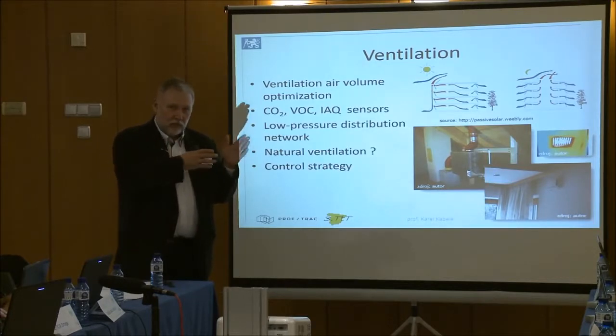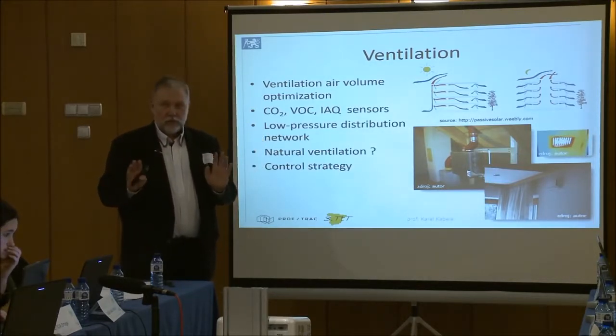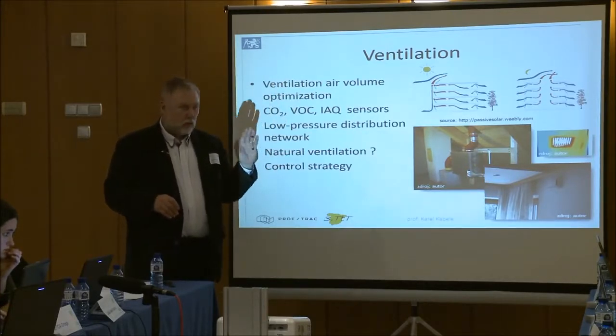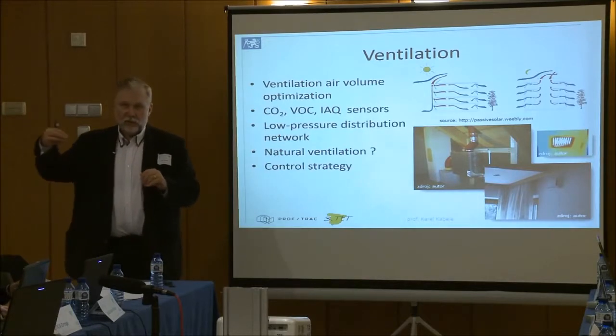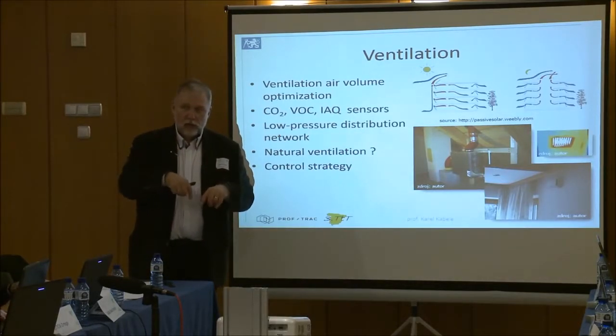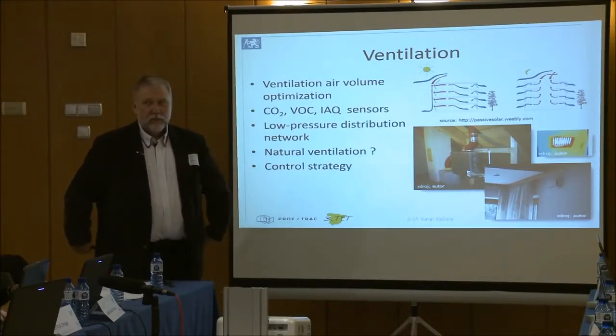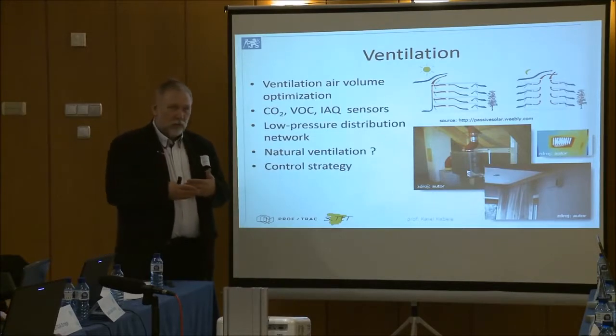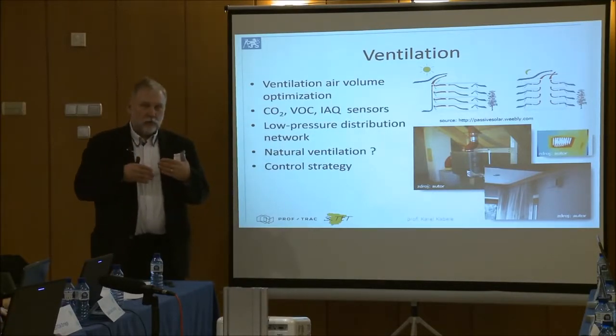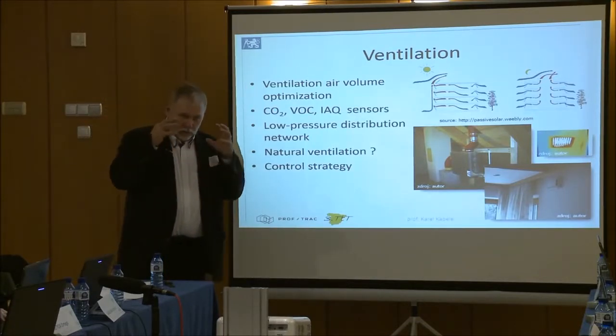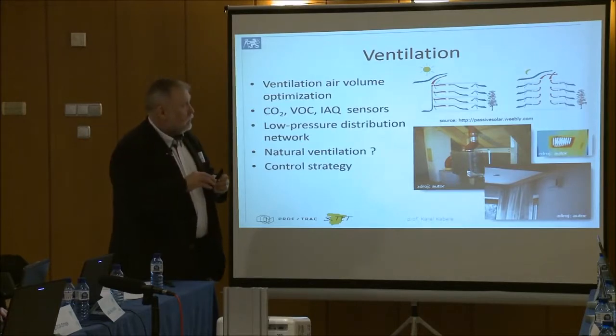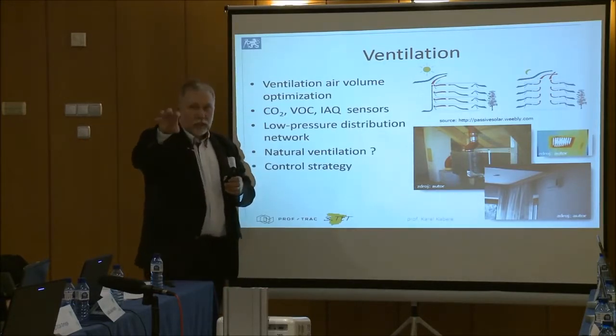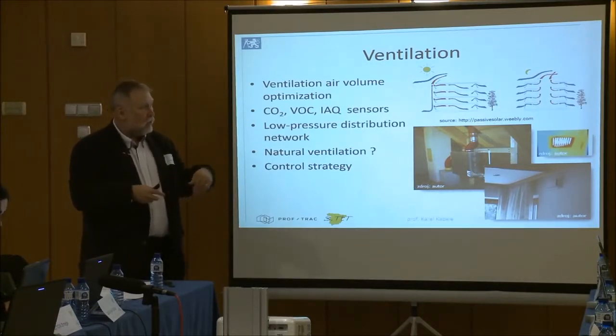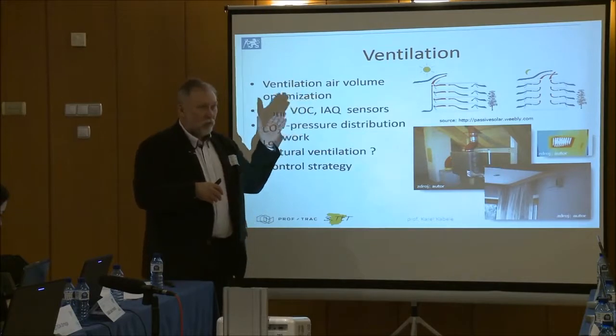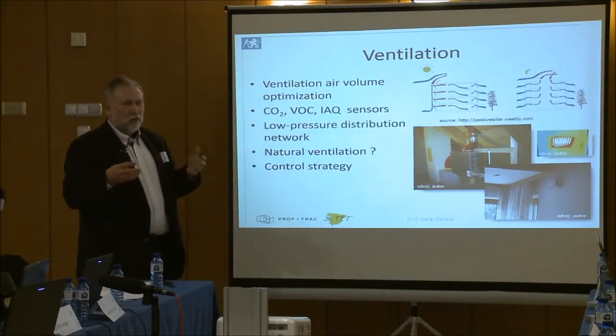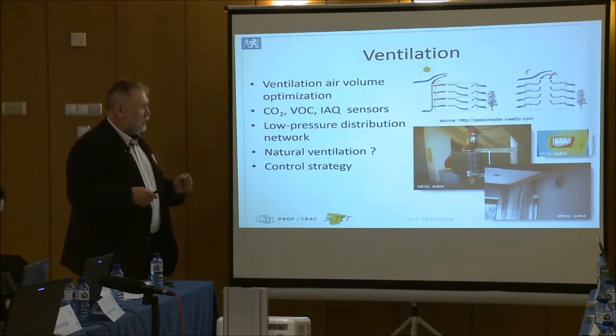In case outside is minus 12, inside is 22, that's comfortable, it's nice, and I'd like to do something like that - then I should be aware that at the moment the air coming into the building is minus 12 degrees, people near those openings will be very, very affected by cold drafts. So comfort in such a building is a big question mark - whether it works or how to do it. Of course it's possible to do simulations, design openings in places not directly affecting humans, but we should think about it - it's not just about creating a nice picture that says it works and it's nice and we don't need any pipes and those stupid machine rooms.